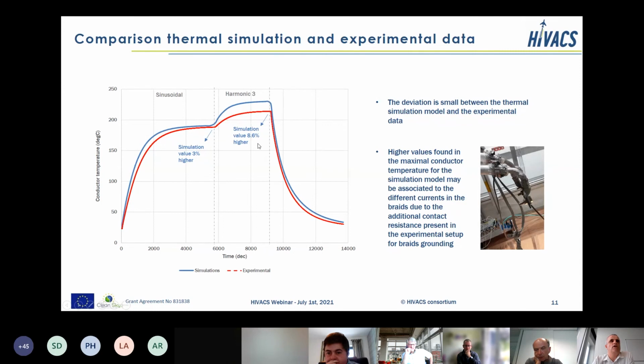When we turn on harmonic 3, it's quite interesting also. We have a little bit more deviation, but it's difficult to understand well. Our assumption today is that maybe there is an important impact of the contact resistance. In fact, it's not easy to connect the ground and to contact all the EMC braid. And as it is an induced-current loop, the additional resistance has an impact on the induced current. So that could be one way to explain why there is more deviation when we put on harmonic 3.